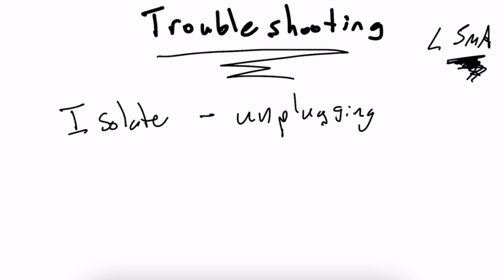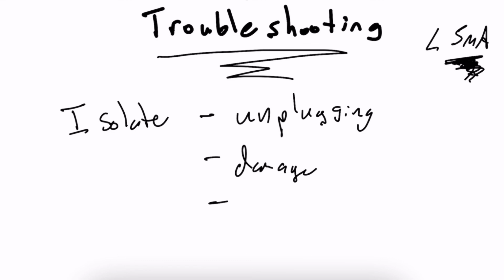But ultimately, what you want to do is isolate the equipment or the pieces of equipment and then figure out what's causing it. It could be that there's damage to the device. Okay, look for damage, do a physical inspection. It could be that the way those devices interact, due to the multiple leads or connections, there's some way the excess leakage current is developing. And there's multiple reasons that that could be happening. There's no hard and fast solution, but at least you can figure out what the troublemakers are, what medical devices are giving you issues, isolate them, and know that that's the problem, and see if you can replace the device, or distance the troublemakers, the multiple devices that are interacting in such a way as to cause a problem.